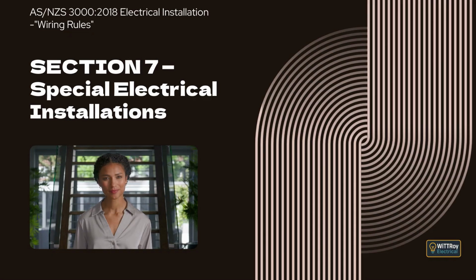1 of the standard. Clause 7.1.1 Application. This clause explains that Section 7 sets out the minimum requirements for how electrical equipment is selected and installed when it is used in special electrical installations. The key idea is that these requirements must be met so that the installation still satisfies the general safety principles of Part 1 of ASNZS 3000, even though the installation itself is unusual or has added risks.